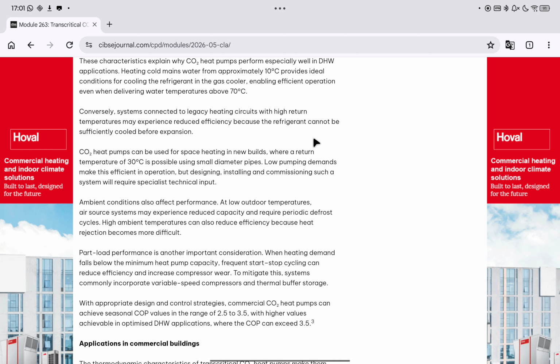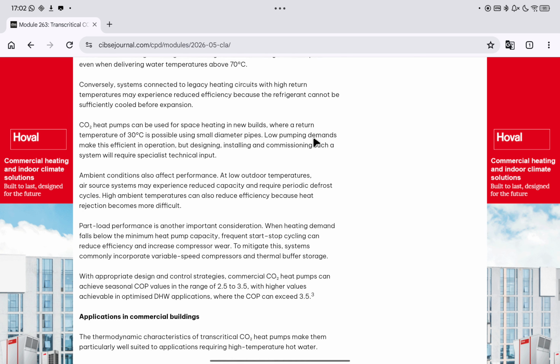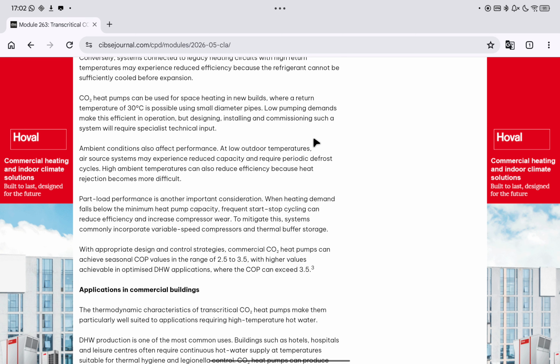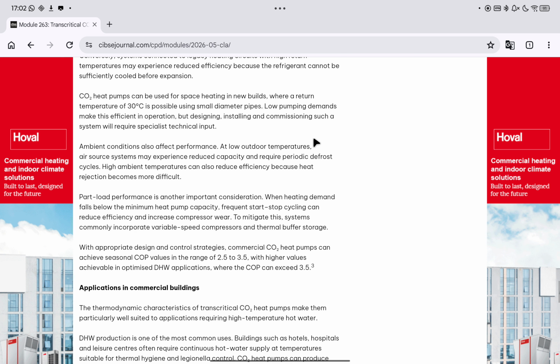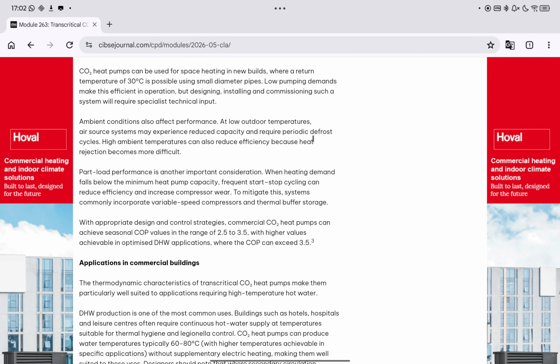At low outdoor temperatures, air source systems may experience reduced capacity and require periodic defrost cycles. High ambient temperatures can also reduce efficiency because heat rejection becomes more difficult. Part load performance is another important consideration. When heating demand falls below the minimum heat pump capacity, frequent start-stop cycling can reduce efficiency and increase compressor wear. To mitigate this, systems commonly incorporate variable speed compressors and thermal buffer storage. With appropriate design and control strategies, commercial CO₂ heat pumps can achieve seasonal COP values in the range of 2.5 to 3.5, with higher values achievable in optimized DHW applications, where the COP can exceed 3.5.